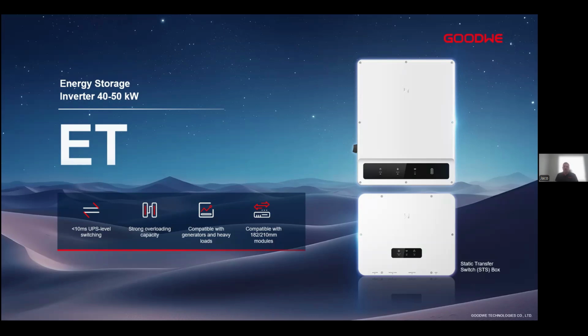Key takeaway here is that in South Africa and in most of Africa, we will mainly promote the 50 kilowatt unit. There are two versions in the series, a 40 and a 50 kilowatt model. But as mentioned, we will focus predominantly on the 50 kilowatt, as the price difference between the 40 and the 50 is quite small. As a full hybrid solution to achieve off-grid capability, the STS is needed. But this unit also has a strong competitive offering for arbitrage and self-consumption. We then do not need the static transfer switch.